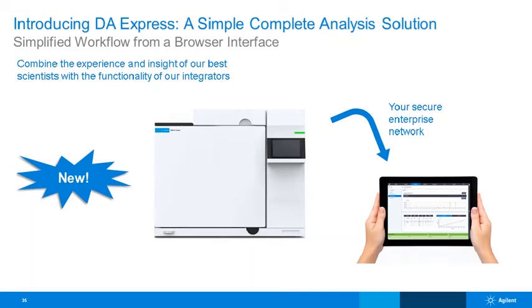So in the past, every instrument had a computer next to it for controlling the GC, for integrating, for calibrating and producing numbers effectively. If we have a computer on board with sufficient memory to store many years' worth of data, then clearly one option is to put the integration and calibration onto the GC itself. And if we do that, then you can control the GC, integrate and produce numbers from the instrument, which is ultimately why you bought the GC. This is particularly useful in academic situations where you have many users, and you may not want a computer next to the instrument. They just basically want to do a simple analysis, connect in with their own computer, do all the calculation, produce the report, and take that report away with them.